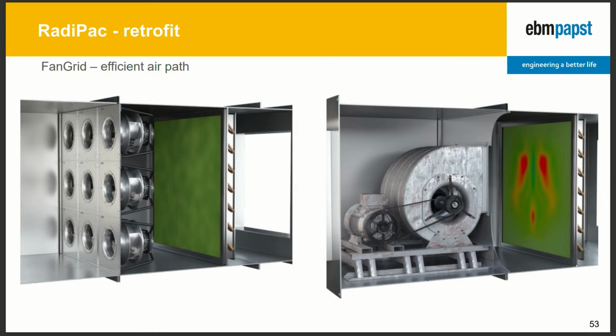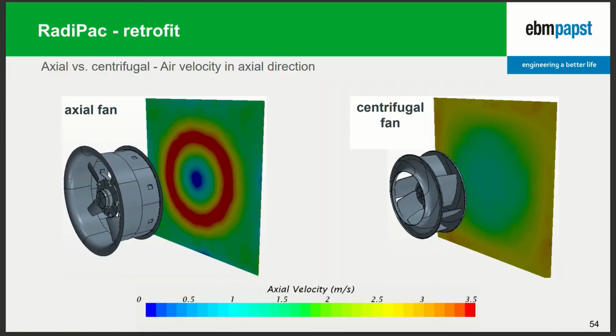This is not the case when you have, for example, such a fan where you have quite a high air velocity out of the impeller. And this is similar to when you use, for example, an axial fan in such an application. Here you can also see the axial air velocity. You can see that in the area of the blades, you have a very high air velocity, and this is negative when it comes to air distribution, when it comes to downstream use of filters and heat exchangers. So maybe an axial fan is not always the best choice when changing from one fan retrofit to another.